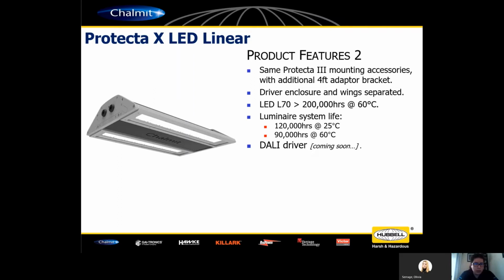That's phenomenal. Now I talked at the start about system life - the time to first component failure, that's the most important part. For most LED products, if not all, that's typically the driver within the luminaire itself. The time to replace the driver within the product is around 120,000 hours at 25 degrees, which is the maximum achievable from the drivers in the product. But I think a more impressive number is the 90,000 hours at the maximum rated ambient of 60 degrees.